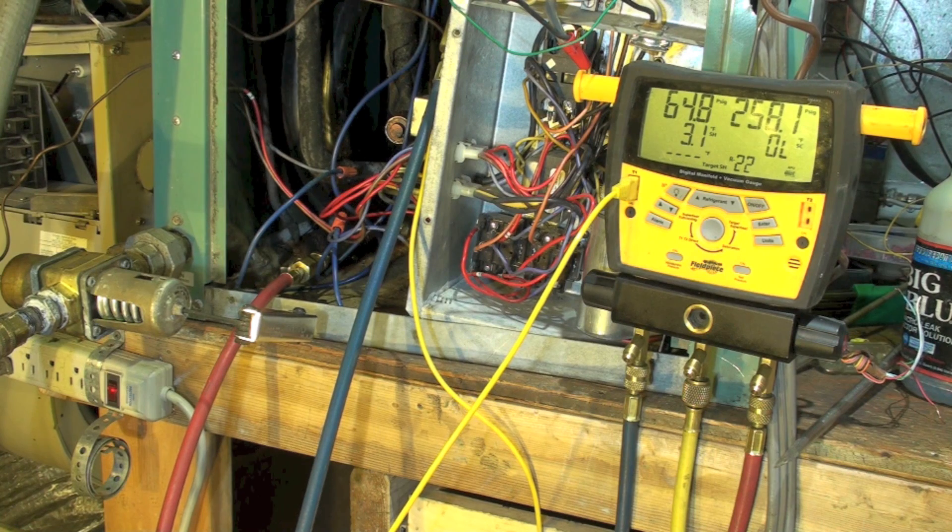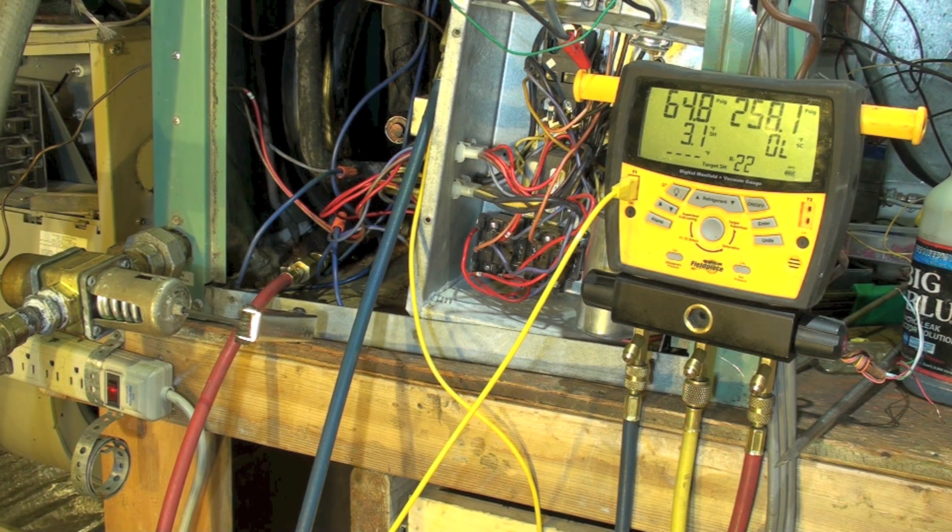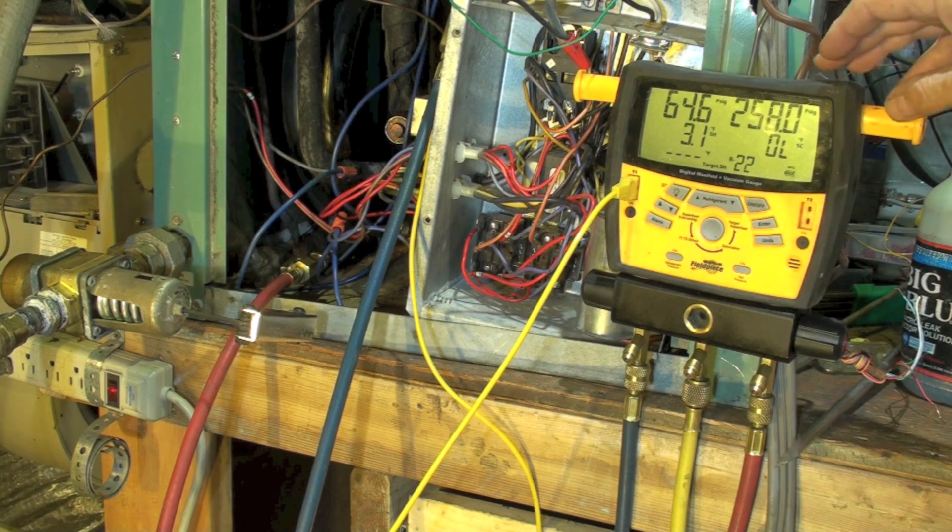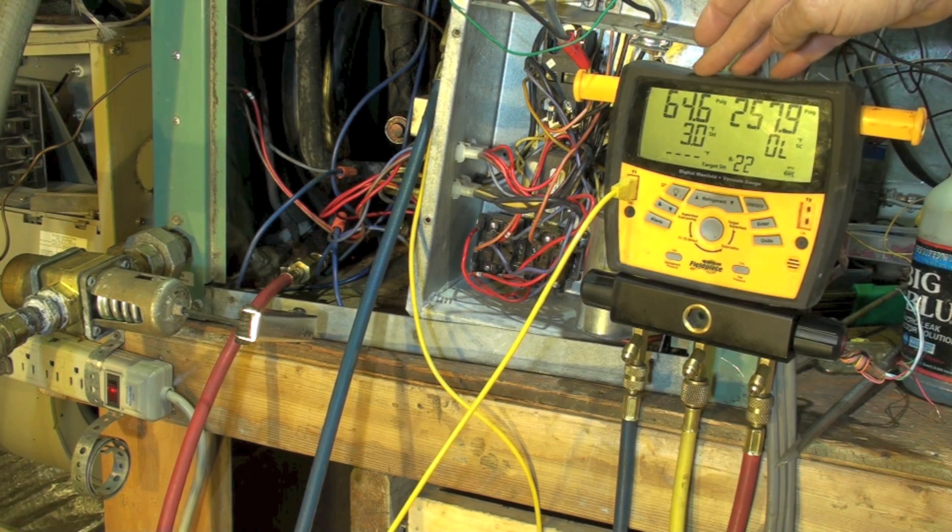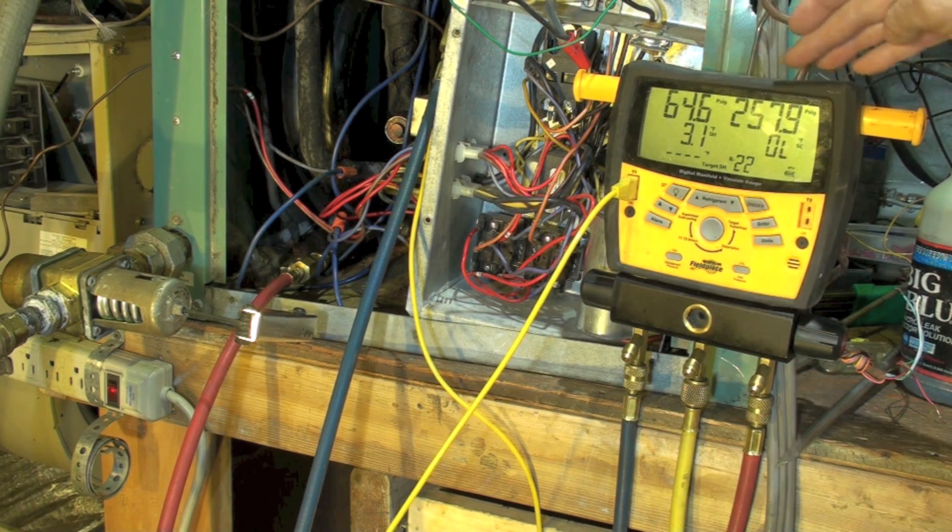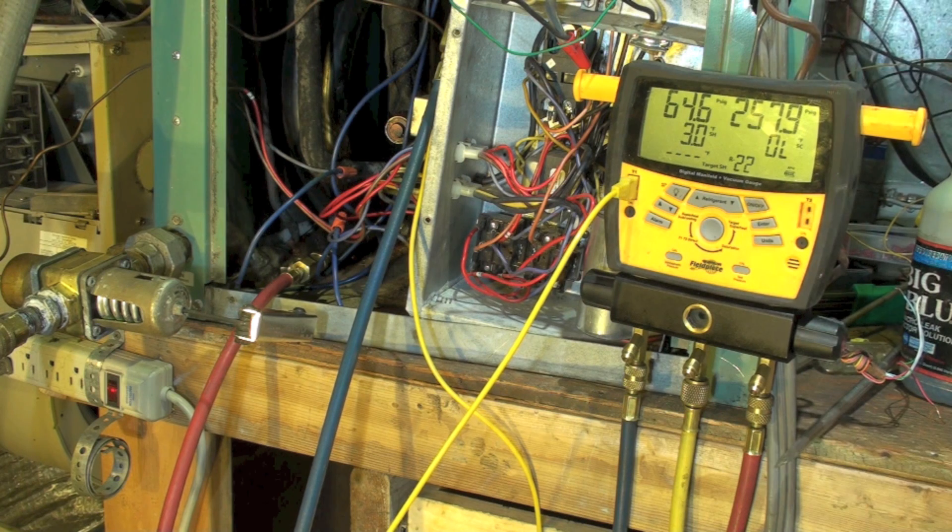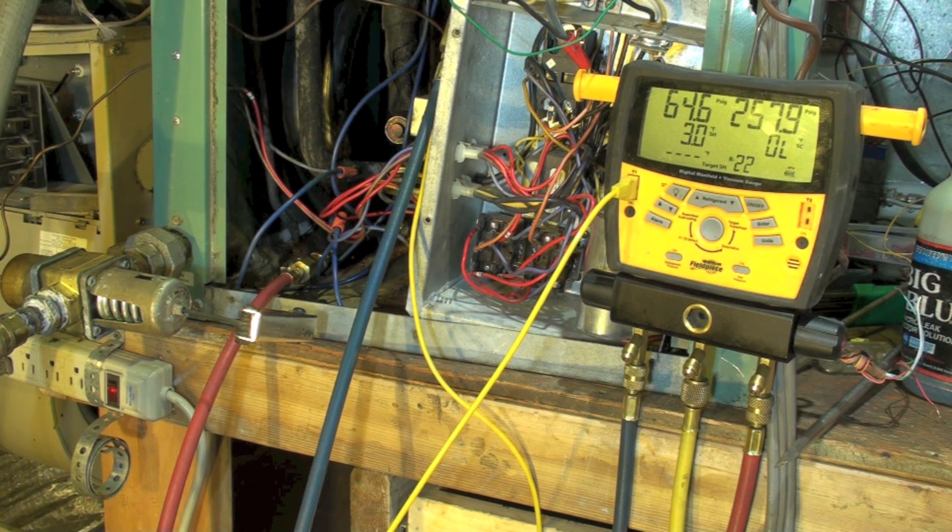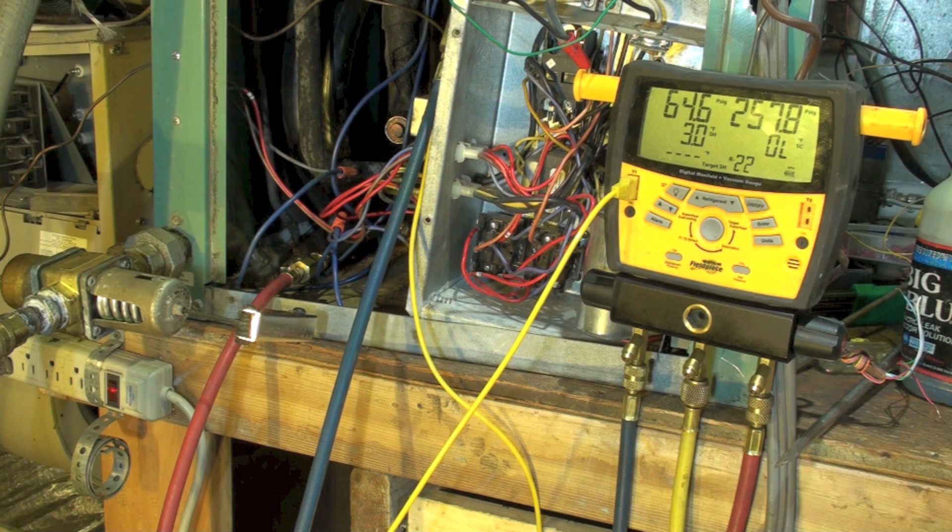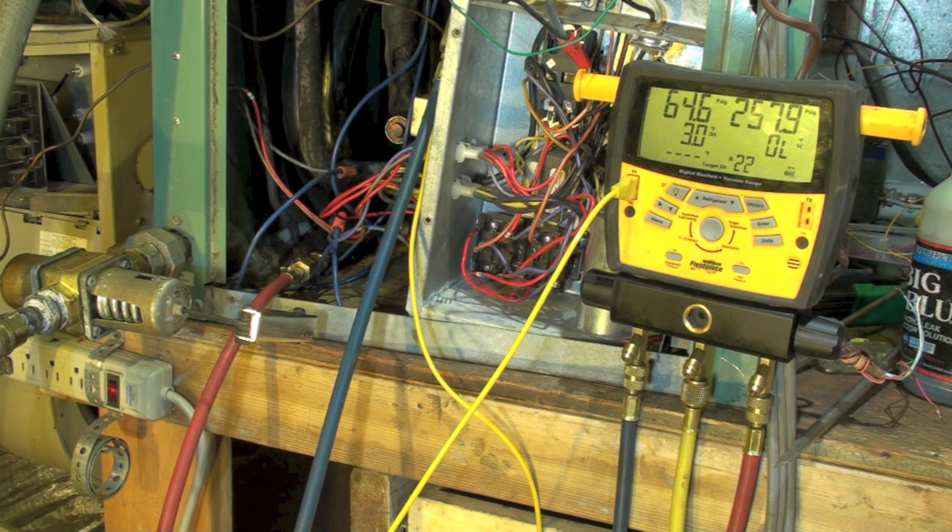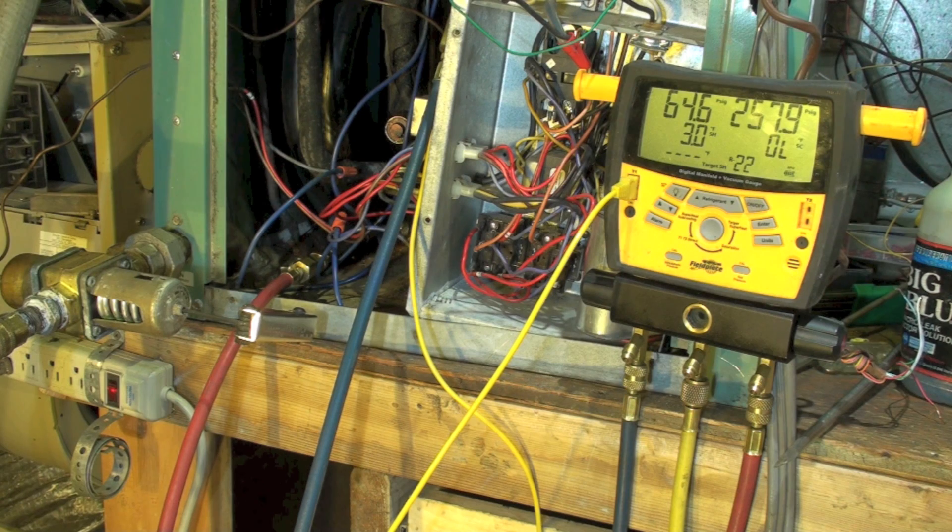So we're at 258 on the head. Now I'm gonna jack it up one more time. Okay, everything's settled down now. My discharge water temperature is 106. If we look at our numbers here, we're running 64.6, 258, and the superheat is still very, very low.